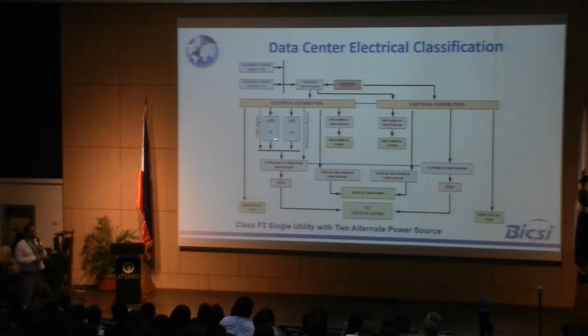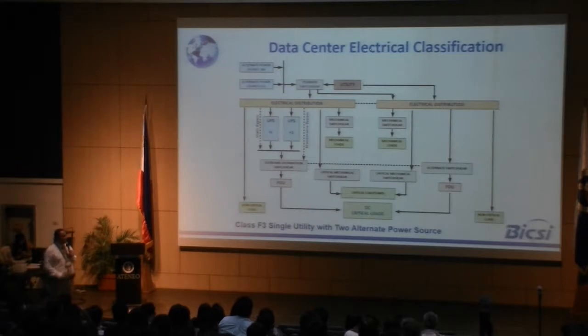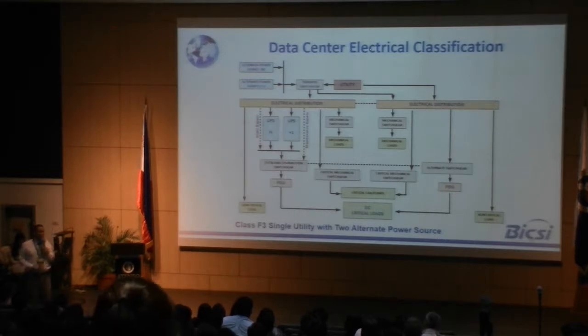When you get to this point, you still have this one, but now with redundant distribution. Then it's tied together—even your outward distribution is still tied. This means if there's a problem here, you can channel the power through here to supply your data center. So there's a redundant supply for your critical loads. Now this is what comes out to your panel boards or your data center—you have two power supplies to your cabinets.